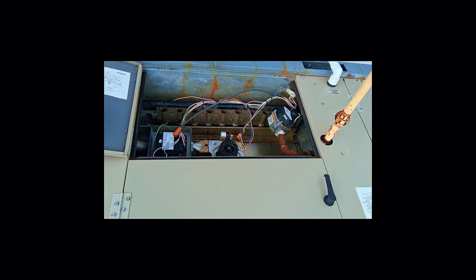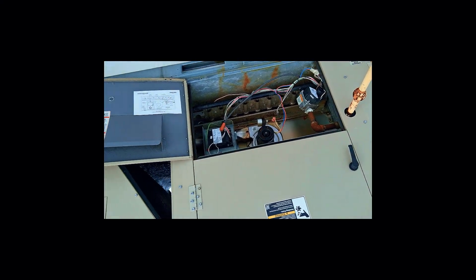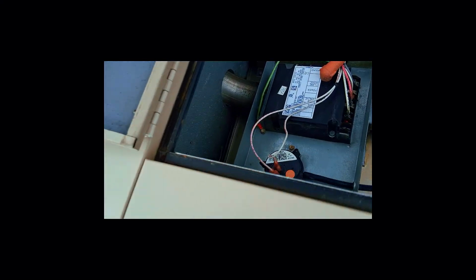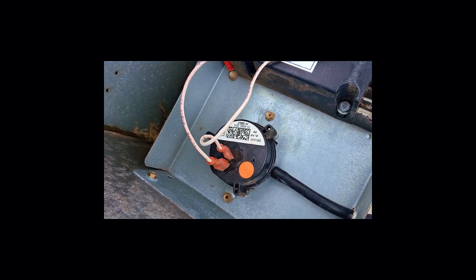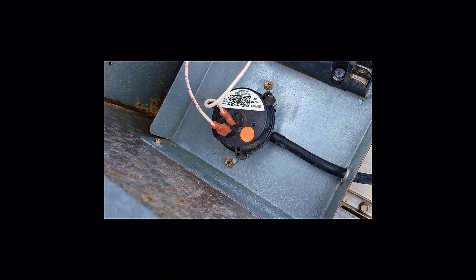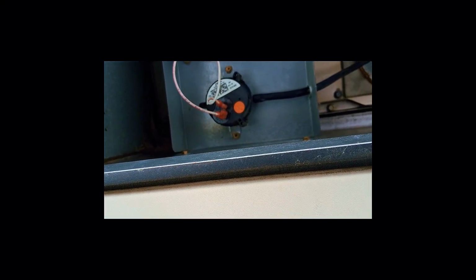So yeah, learned something new about Lennox today. Hope you guys have too. With these Lennox Prodigy control boards, even when the inducer motor is not running, the board sends some microamp voltage toward the proving switch, the air switch, which gives you a continuity reading on your meter even though it's not really telling you that it's closed. It's just the board sending a signal through there to monitor that switch.